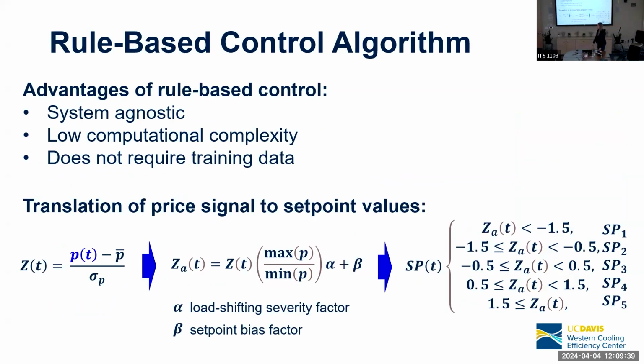For our rule-based control algorithm, some things to note: it's system agnostic. Because we're just sending out set points, it's not taking over any of the controls proprietary to this device. It has really low computational complexity, and it doesn't require any training data. It's purely rule-based, there's no model, so we don't have to know very much about prior system operation.